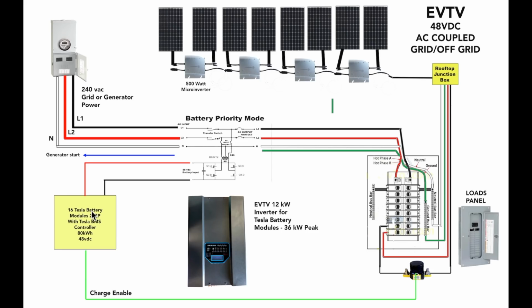batteries. And everyone will tell you this won't work, including the manufacturer of this inverter, who has described for me in detail why this won't work. And I can measure it all day long, and it not only works, it's flawless. It works fantastically. Up to the point where the batteries get full, and I disconnect the battery to prevent overcharging the battery with the battery controller. At that point, all hell breaks loose. But the basic concept is the inverter, of course, shuts down because we've cut off the battery, and then the inverters shut down. And hopefully all that happens in an orderly fashion, but not necessarily.